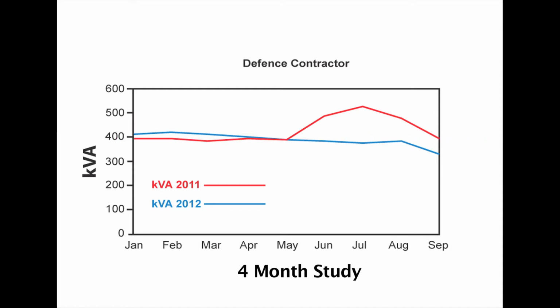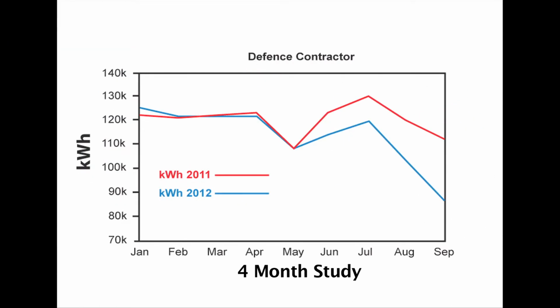This dotted line indicates the limit PowerGuard was adjusted to, and it clearly indicates that the 400 kVA limit was never exceeded. This proves the point that the peak demand is effectively restricted to the set limit, and that a secondary peak is eliminated. The kilowatt hours graph indicates the same tendency to diverge once PowerGuard was installed, suggesting a considerable saving in consumption as well.